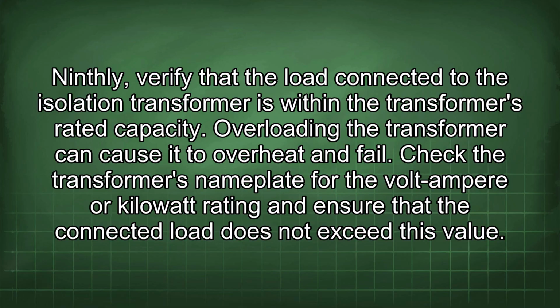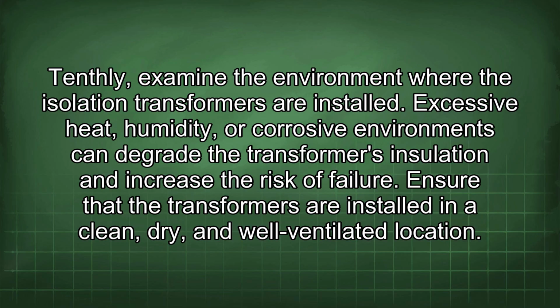this value. Tenthly, examine the environment where the isolation transformers are installed. Excessive heat, humidity, or corrosive environments can degrade the transformer's insulation and increase the risk of failure. Ensure that the transformers are installed in a clean, dry, and well-ventilated location.